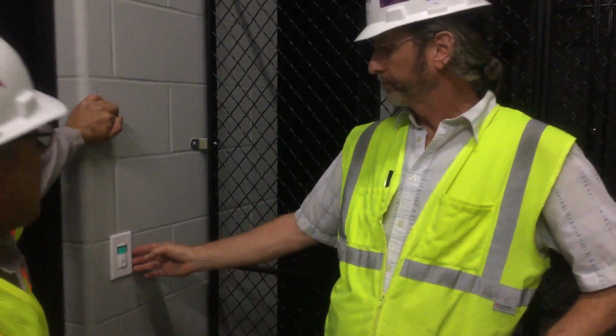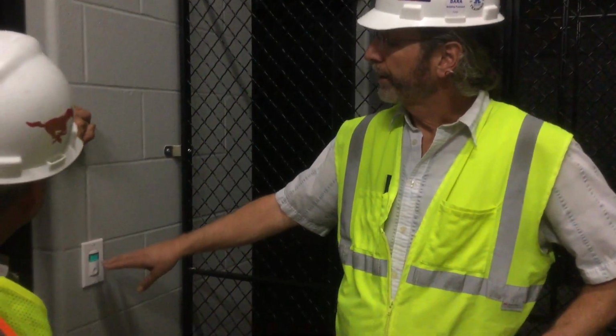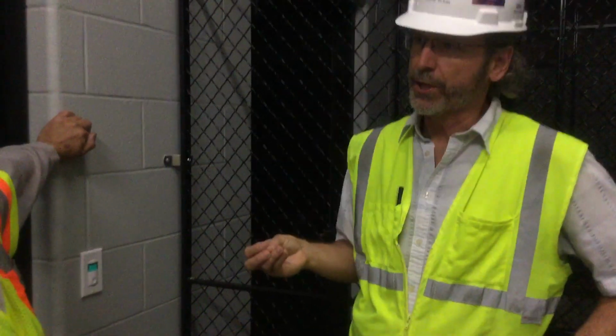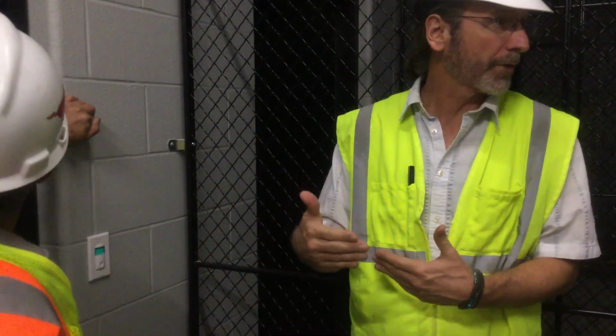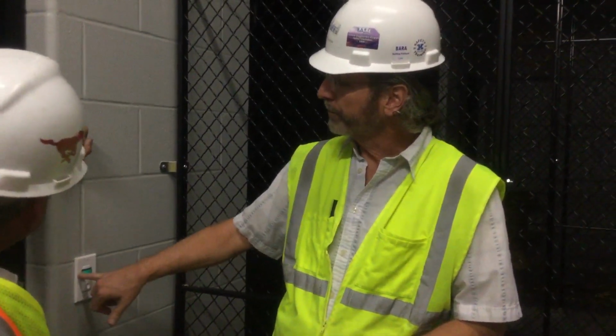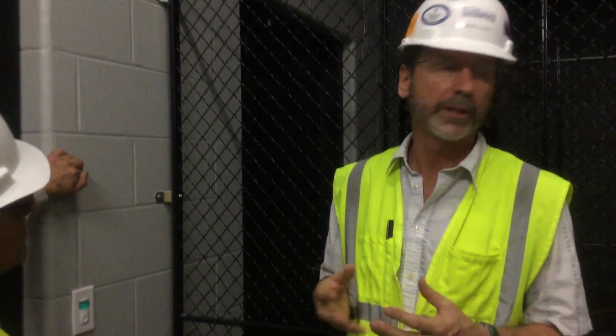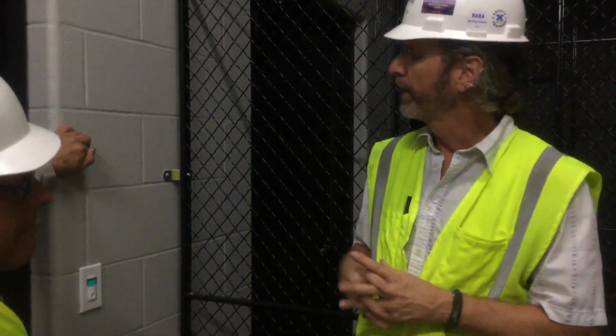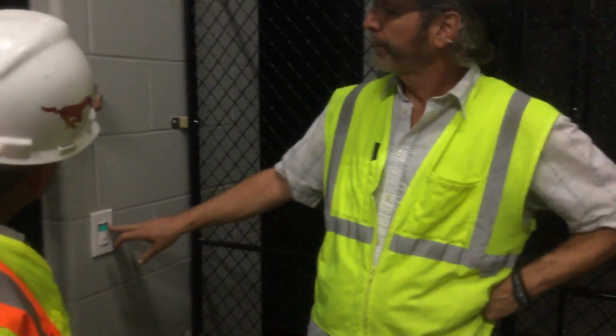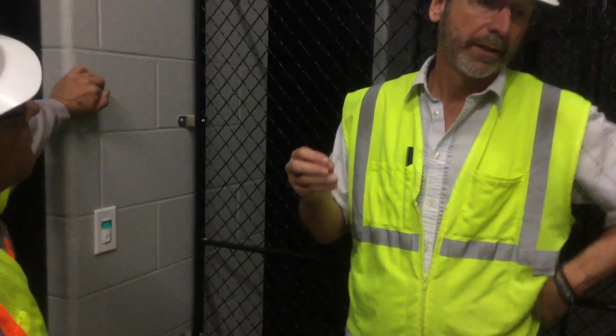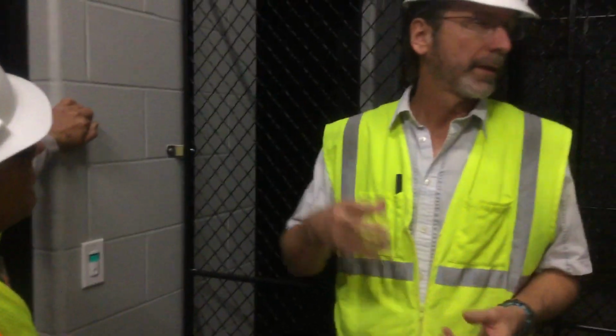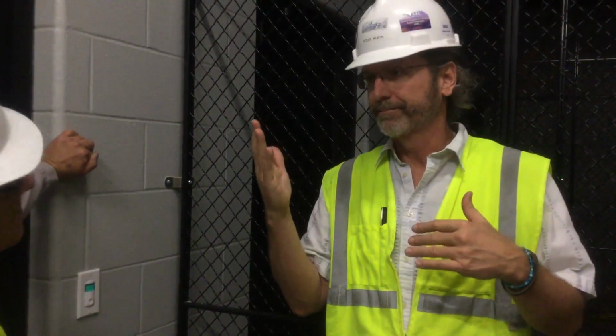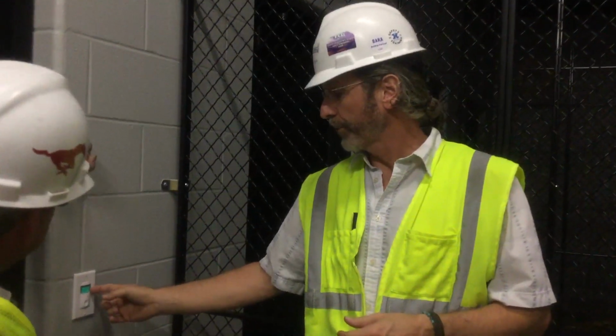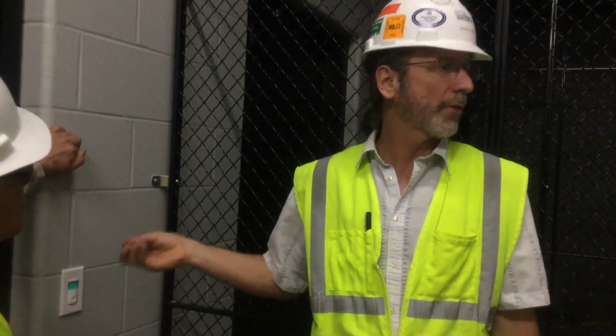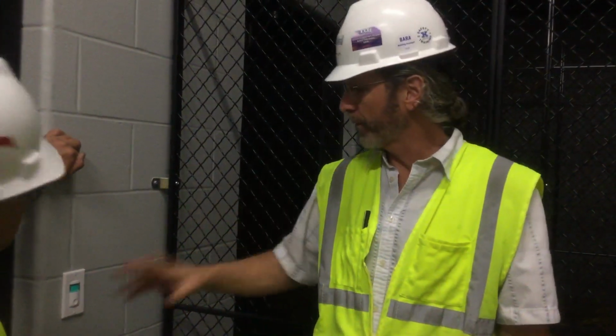That 3 hour default time delay can be changed. There's a procedure in the instruction manual. Take the cover off and press the button, and you can change that default time to whatever you want. So you can set it back to 20 minutes or 10 minutes or whatever is good for you. There's also a feature that you can turn on or turn off that several minutes before it's about to turn off, it will flash the lights off and back on. And then there's another feature that you can turn on or turn off. It does a little chirping sound right before the lights are going to turn out. So just be aware of that.